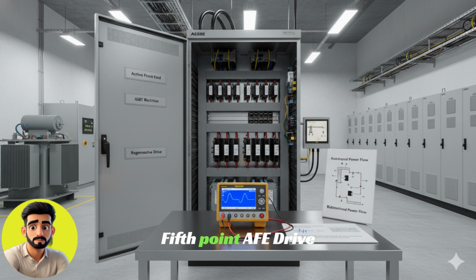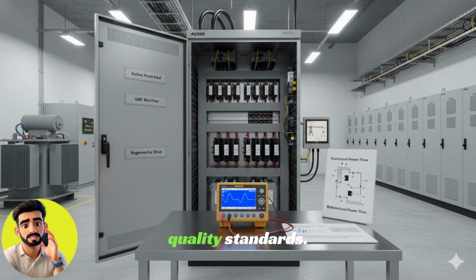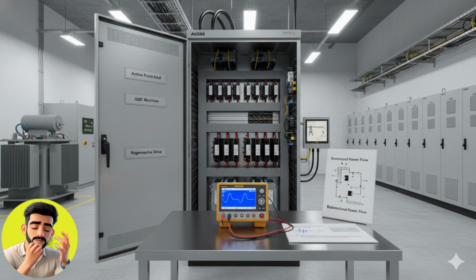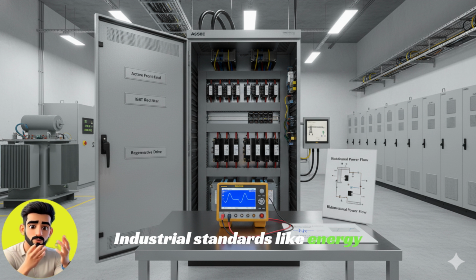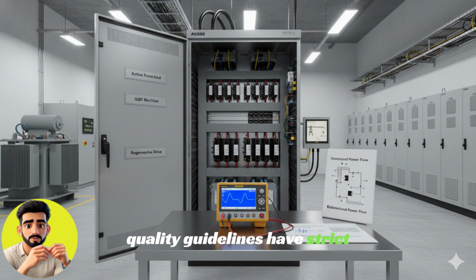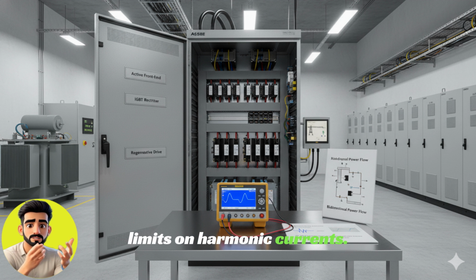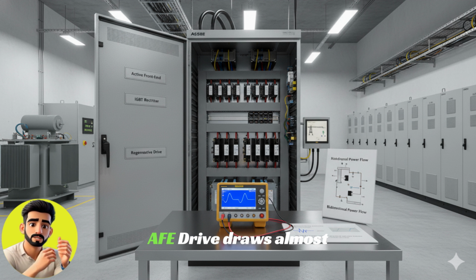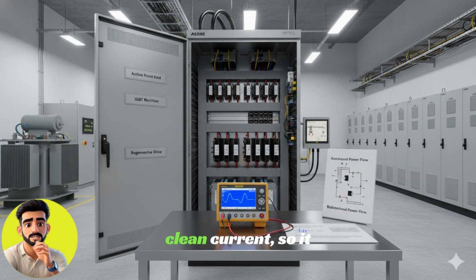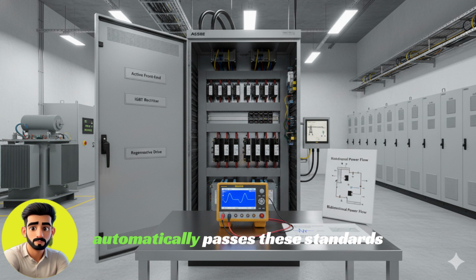Fifth point, AFE drive easily passes the power quality standards. Industrial standards like energy quality guidelines have strict limits on harmonic currents. AFE drive draws almost clean current, so it automatically passes these standards and does not require additional filters.